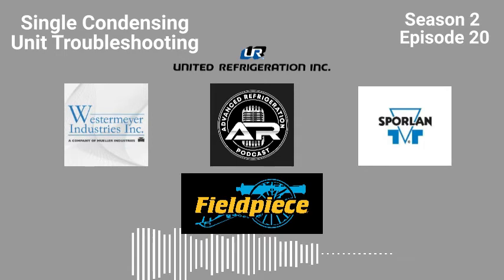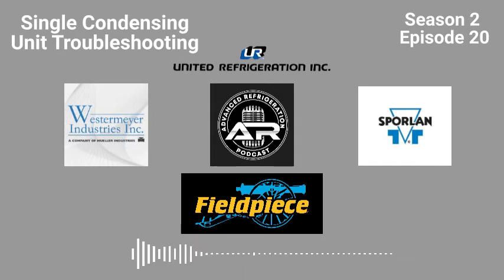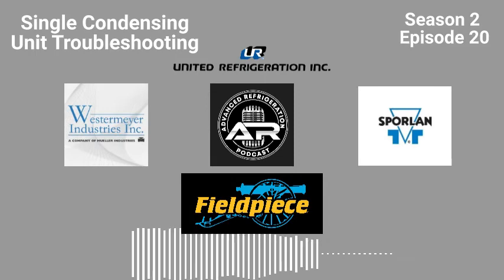Jumped up to 69,000. So just going from 107 to 85, jumped it up 7,000 BTUs. I mean, that's a decent amount, but if the whole load is, that's almost an eighth of the load. Once again, it's like putting another case on there, right? Yeah, to be honest, I think these should be undersized slightly.